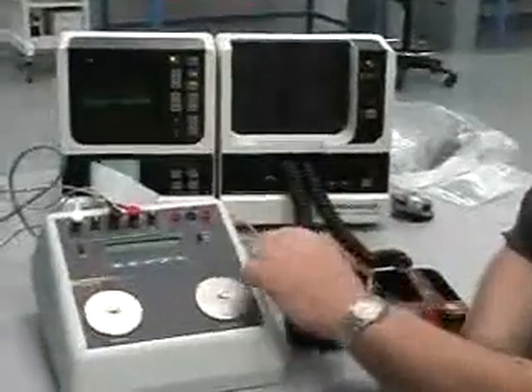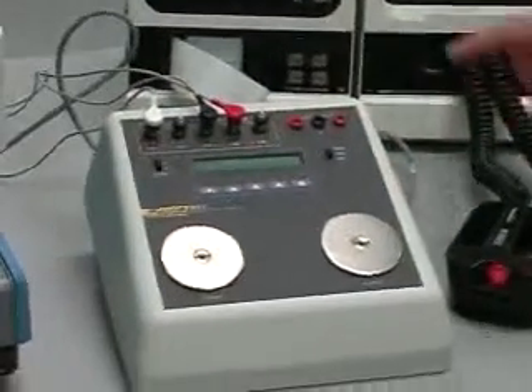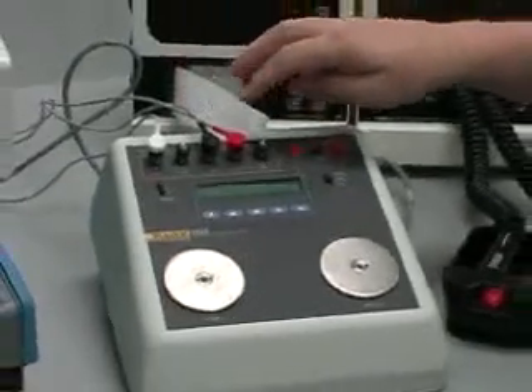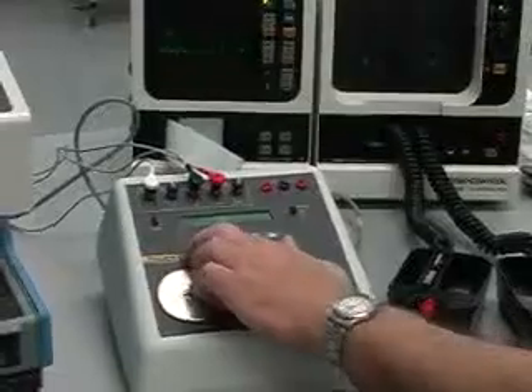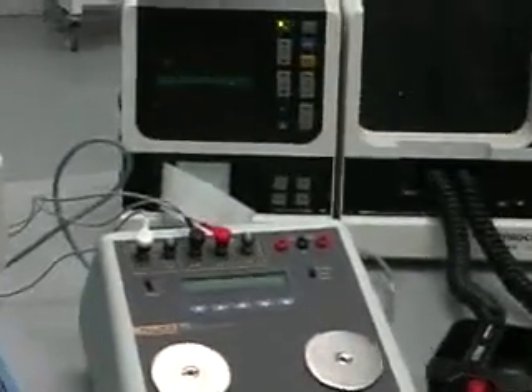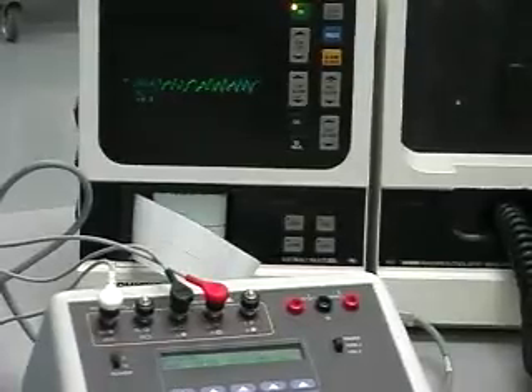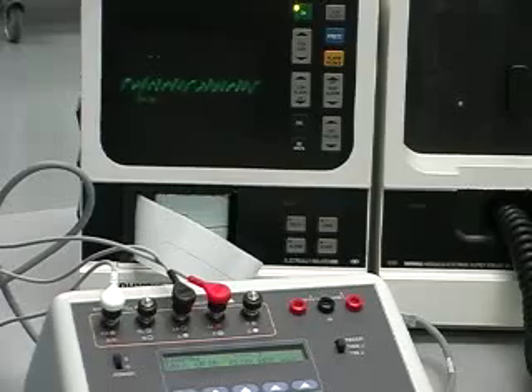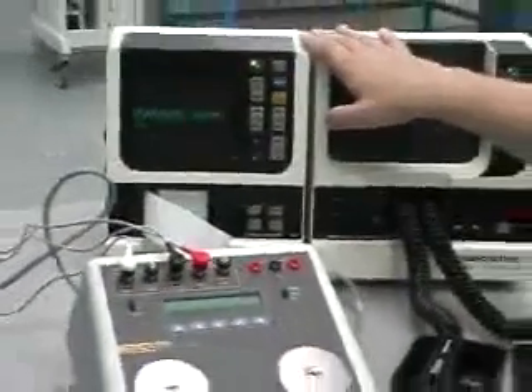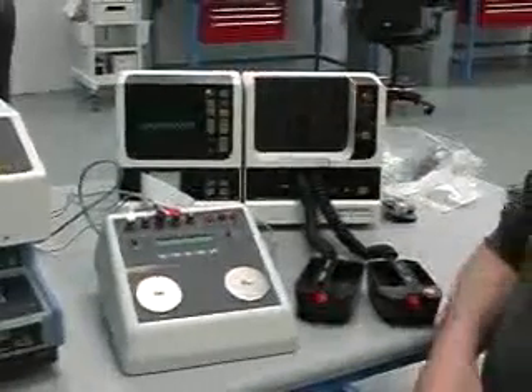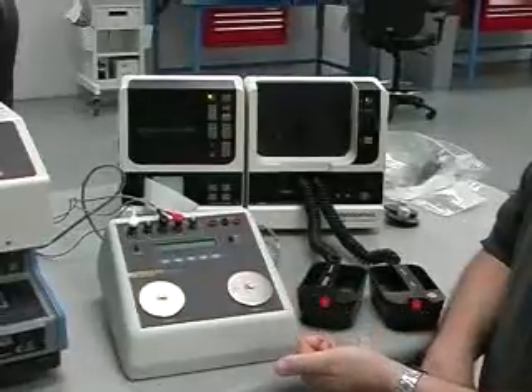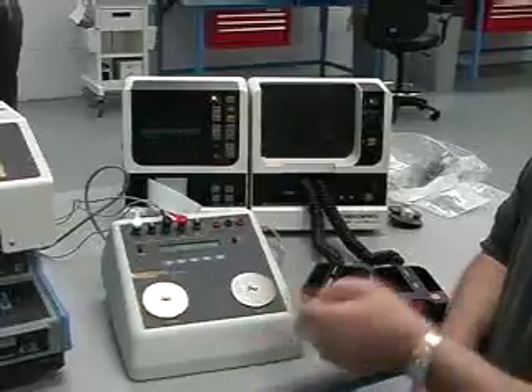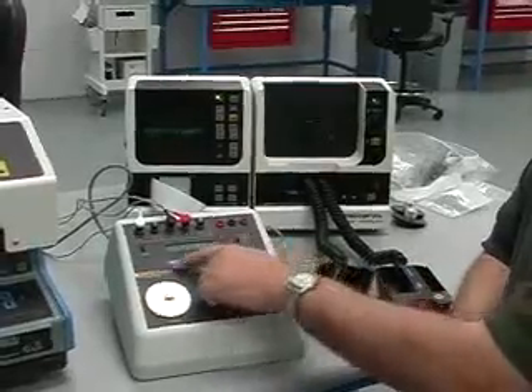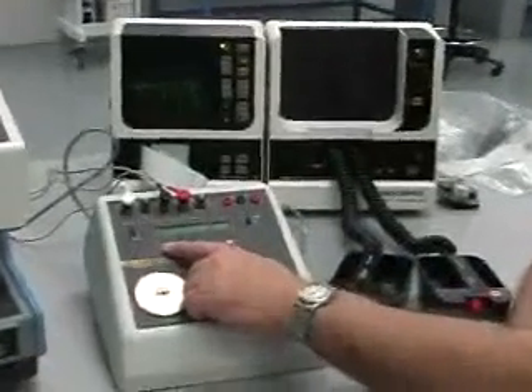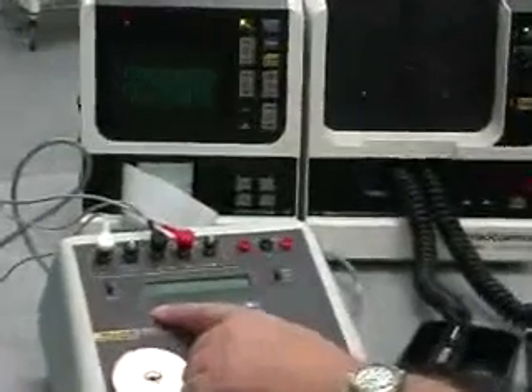As you can see, we always output an ECG waveform during this test, and you can change it to fit the different types of defibs, or custom select a waveform specific to the type of defibrillator you're going to be testing. This is a manual defib with no interpretation capabilities, so it's not really being used, but I wanted to show you that initially it will output a normal sinus ECG at 90 beats per minute, or for testing the automated units, it will output a VFib waveform, and then also VTAC, and several different selections of VTAC.